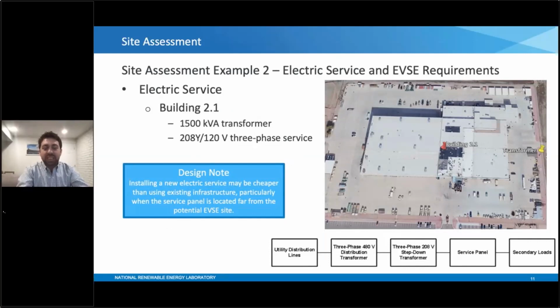But one thing to note at the bottom right here, the setup for this particular facility was that they had to still own a portion of their transformers. As I mentioned before, some facilities own their transformers, while the utility owns them in most cases. In this case, the utility provides them a 480 volt service from their distribution transformer. And then the facility has a step-down transformer that goes from about 480 volts down to their typical industrial voltage, 208Y/120 volt 3-phase service.